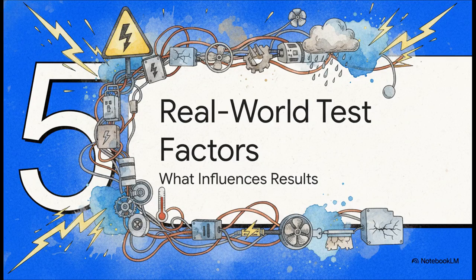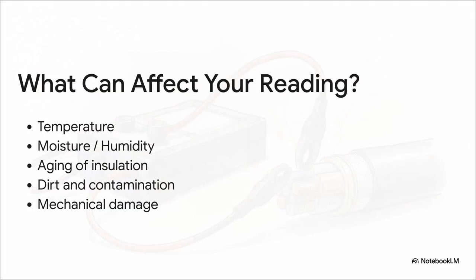But here's the thing. A reading isn't just a number in a vacuum. The real world has a way of influencing your results, and you've got to be aware of what's going on with the equipment's environment. A bunch of different things can mess with your reading and make it look lower than it is. For example, higher temperatures can make insulation a little less resistive. Moisture and humidity are a big one. They give current an easy path to leak out. And of course, the physical condition is huge. Old, dirty, or damaged insulation is just not going to perform well. It's so important to think about these conditions when you're looking at your results.